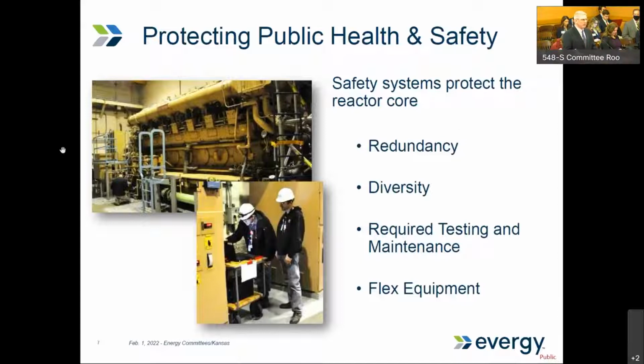Typically, in most cases, they don't actually operate on a daily basis. But if there's a change in parameter as prescribed, they would actuate and start flowing water, provide power, whatever the function might be. Because we need redundancy, we have at least 2, in some cases 3, of those systems. From a diversity perspective, they'll be in different parts of the room so that if some event affects one room, it won't affect the function of both pumps. These are fundamental design requirements standard in the industry.